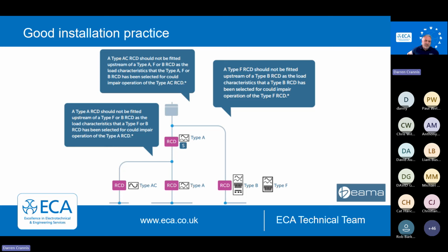Good installation practice. Now, we highlighted this earlier. There's a fundamental difference between type A and type AC, and type B and type F devices. They are two different British standards. Importantly, the type A and the type AC have a tolerance to DC. They can't detect DC. They have a tolerance to it. The AC having a tolerance of none, the A having a tolerance of 6 milliamp. Well, it will still function.